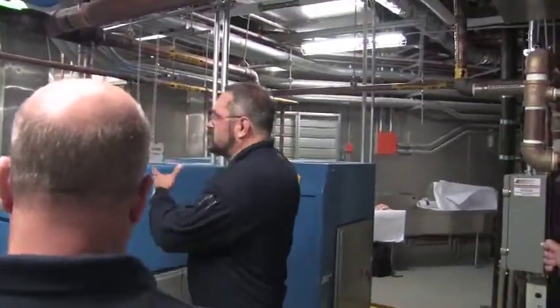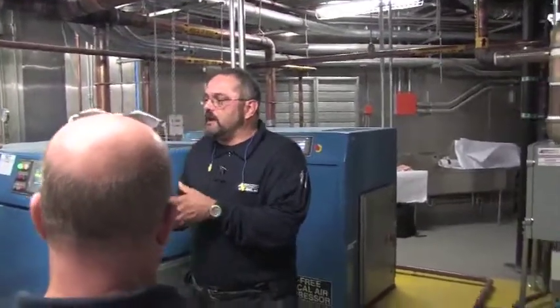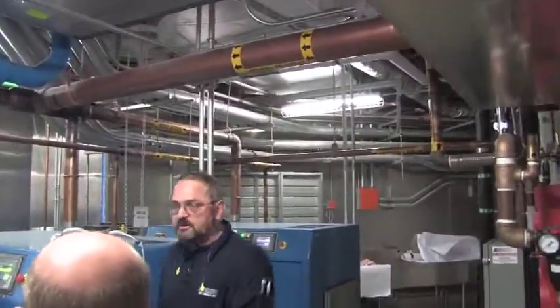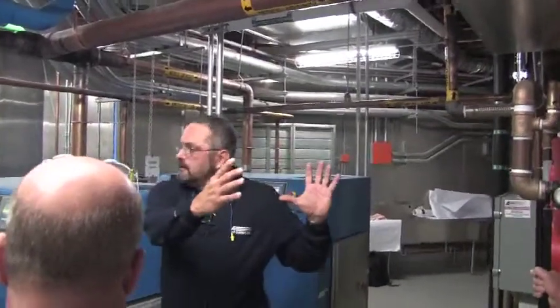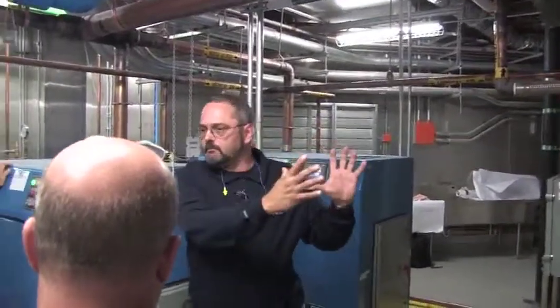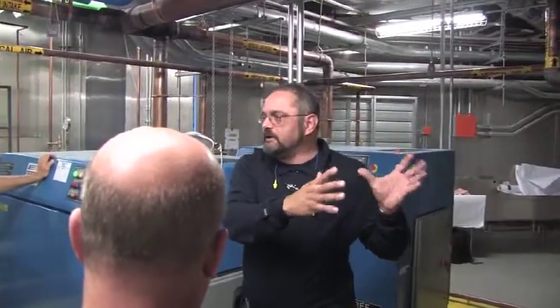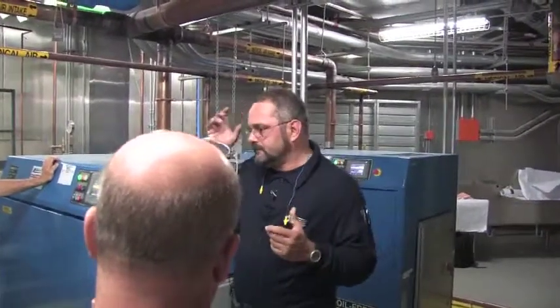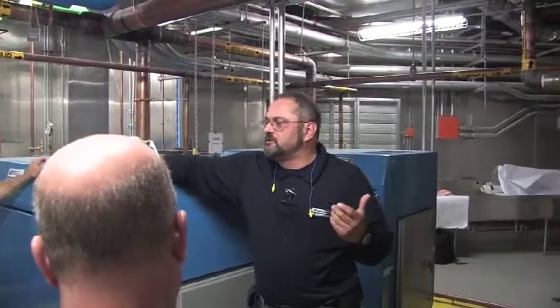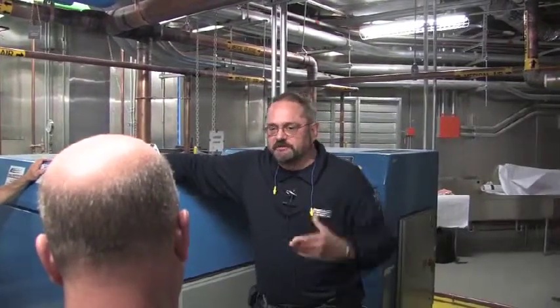We have three identical machines. The other way to build this type of thing would be three identical machines and a sequencer box on the wall here. So all three machines rotate based on that sequencer box. The only difference they've done is for ease of use. They start doing separate sequencer boxes if you have more than 5 machines. They can do this type of thing for up to 5. They'll try to convince you to put a separate sequencer on if you go over 4, but they can do up to 5 on this configuration.